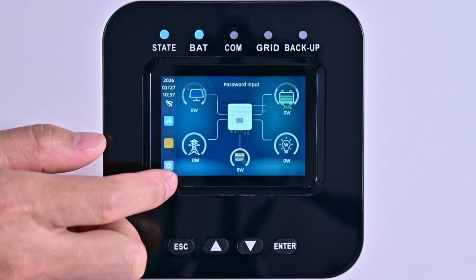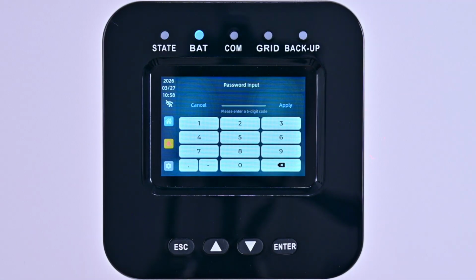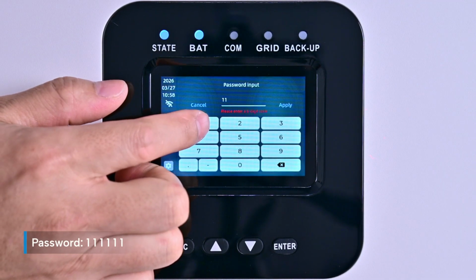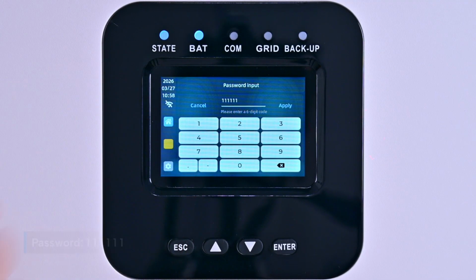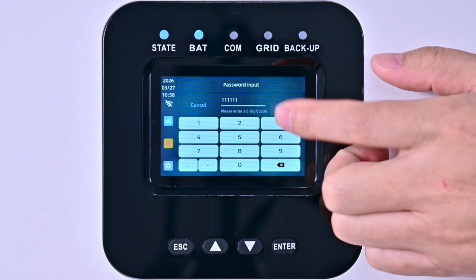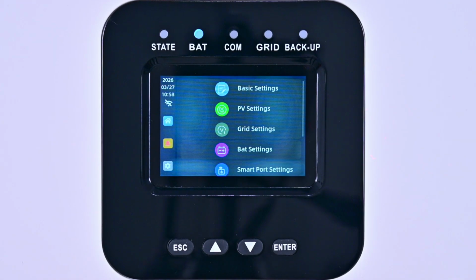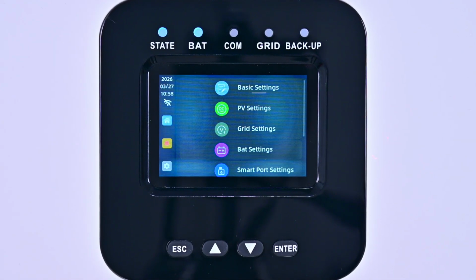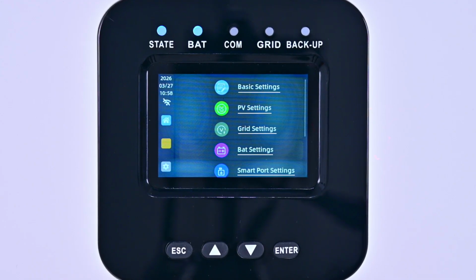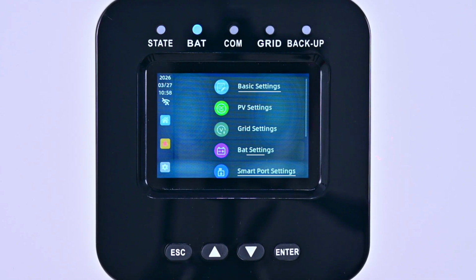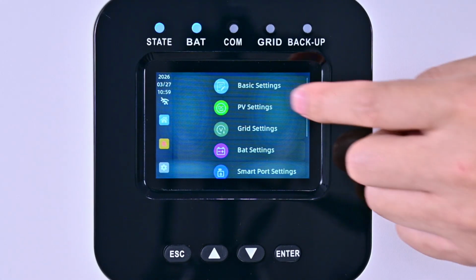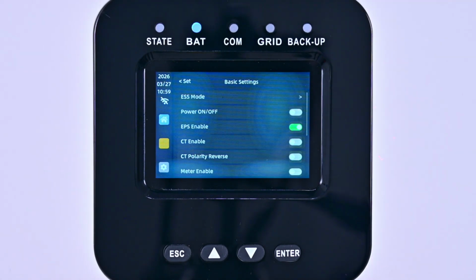Tap the gear icon in the bottom left corner of the screen. Enter the administrator password, 6 ones, then tap Apply. This is the device's complete settings interface. Different settings are categorized under various tabs such as PV, grid, battery, and port control. Tap Basic Settings to view details. We can see that Power On-Off and CT Enable are currently disabled. Since we installed the current transformer earlier, we will enable CT.